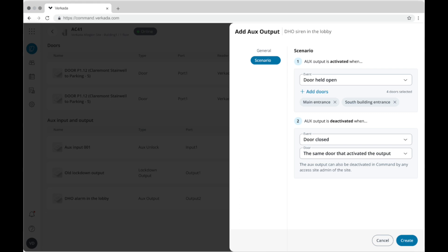There is no fire relay interface on this, so if you're looking to bring down the door purely from a hardware switch, you need to install a power supply or a power controller and run your fire relay that way. Last but not least, you also have an auxiliary port — as we announced recently, that will allow you to create a deterrence by having things such as lights or sounders that go off in case the door is held open or forced open.